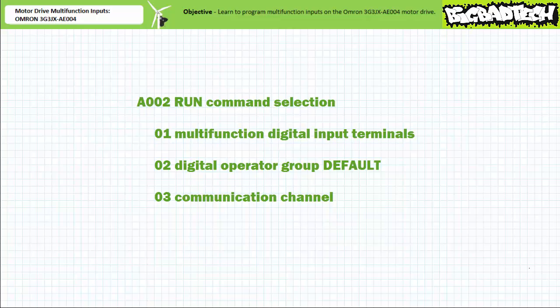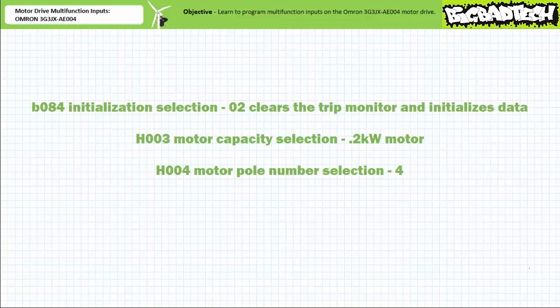Before navigating to and changing these parameters, let's establish a base state, establish a common language, and install some external devices. Before making use of the OMRON 3G3JX AE004 motor drive, we'll initialize the drive to a default state and clear any errors using initialization selection parameter b084. Then we'll program it to recognize a 200-watt motor with a nominal rotational speed of 1800 RPM using the motor settings parameters H003 and H004.